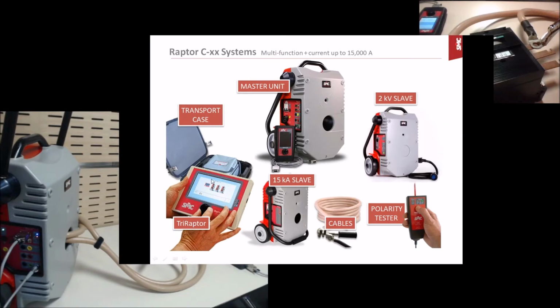This is the special commander for the 3-phase Raptor. Then the transport case that you can also see here. The extra flexible cables that we recommend for the Raptor, because they allow you to do the multi-turn feature as we are using in this example today, and a small probe that will let you very quickly check the polarity, the connections in any AC installation. With the Raptor injecting a codified signal, this small probe will show you with a green or a red LED, and an audible beep, if a connection is the wrong polarity.